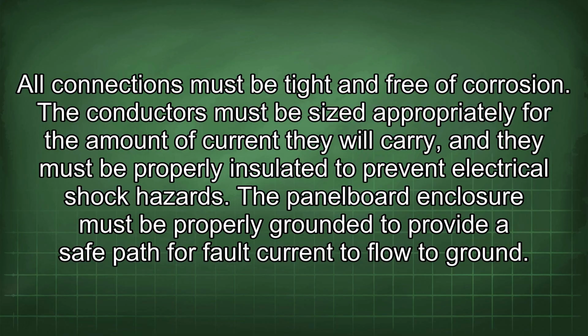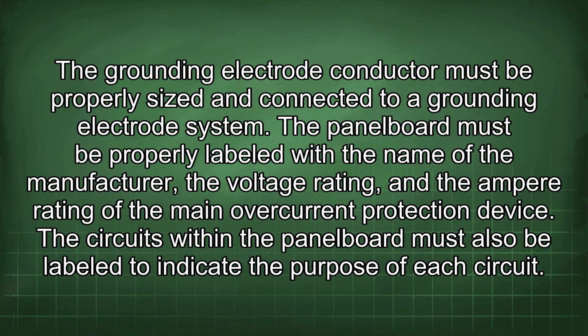The panelboard enclosure must be properly grounded to provide a safe path for fault current to flow to ground. The grounding electrode conductor must be properly sized and connected to a grounding electrode system. The panelboard must be properly labeled with the name of the manufacturer, the voltage rating, and the ampere rating of the main overcurrent protection device. The circuits within the panelboard must also be labeled to indicate the purpose of each circuit.